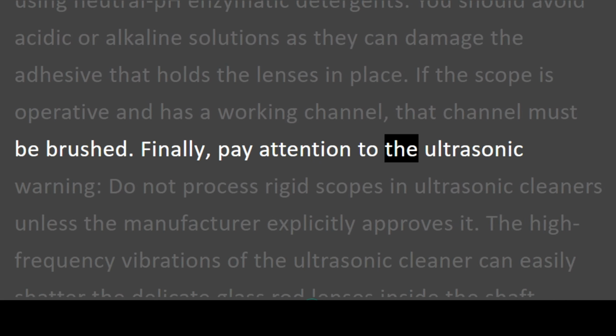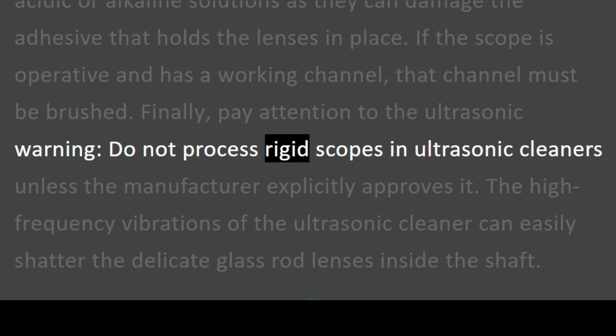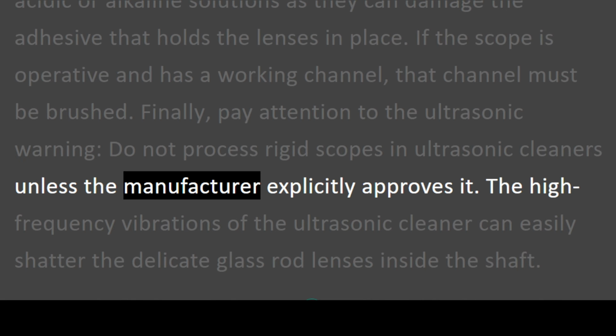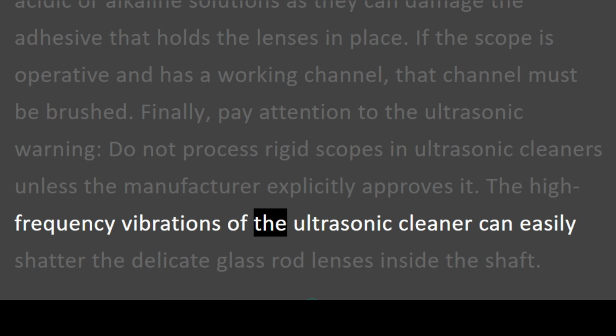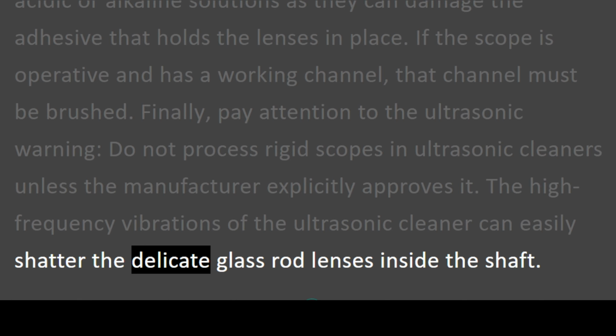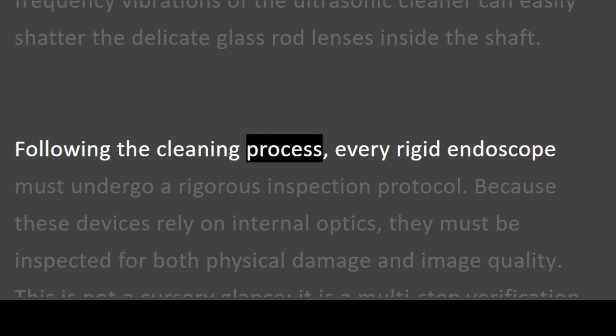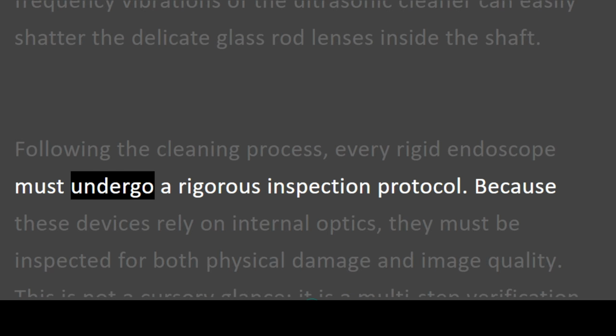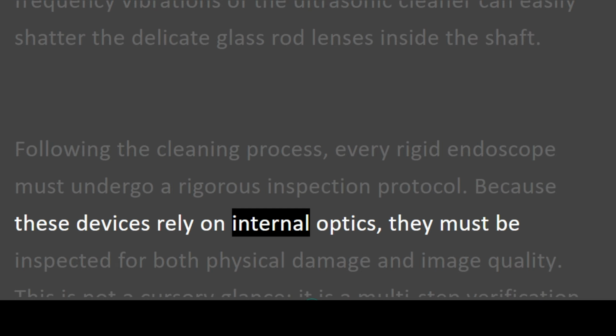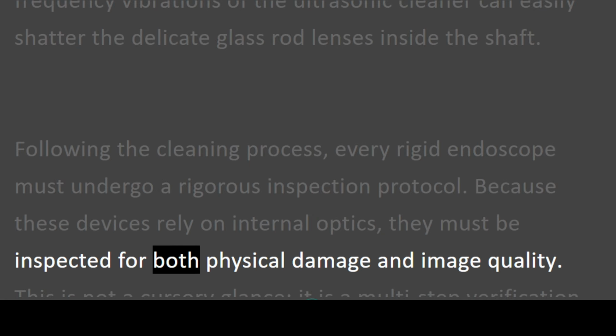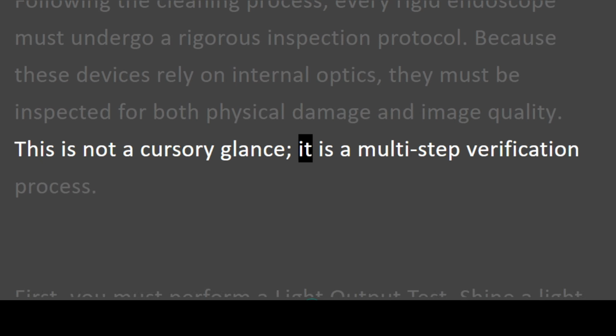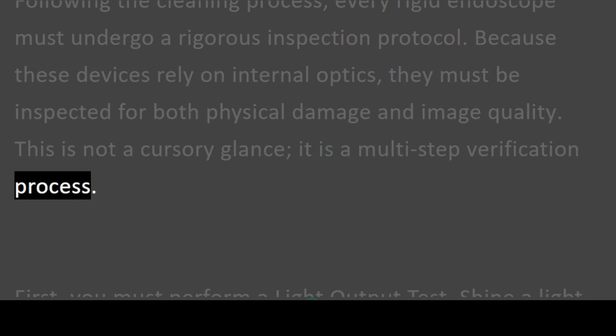Finally, pay attention to the ultrasonic warning. Do not process rigid scopes in ultrasonic cleaners unless the manufacturer explicitly approves it. The high-frequency vibrations of the ultrasonic cleaner can easily shatter the delicate glass rod lenses inside the shaft. Following the cleaning process, every rigid endoscope must undergo a rigorous inspection protocol. Because these devices rely on internal optics, they must be inspected for both physical damage and image quality. This is not a cursory glance, it is a multi-step verification process.